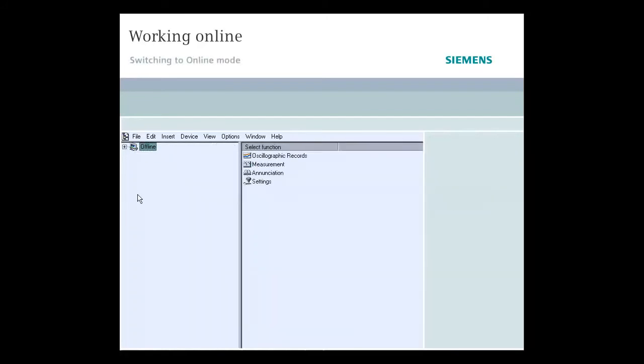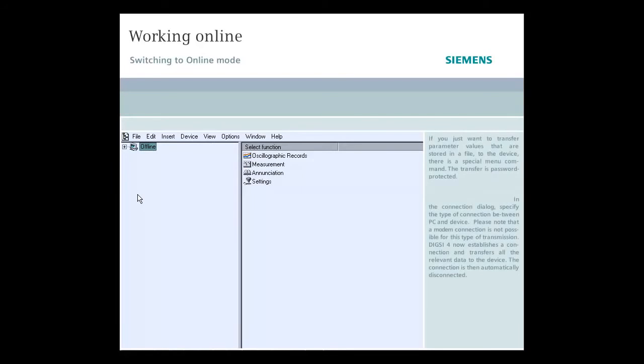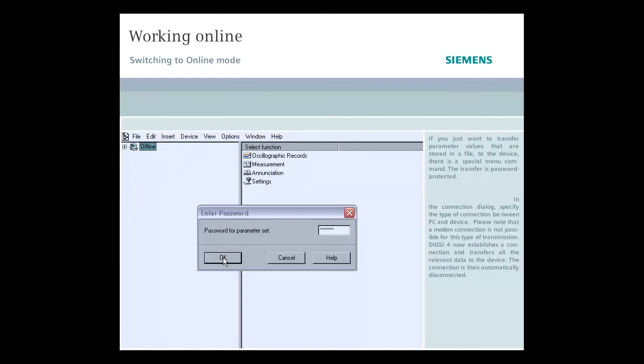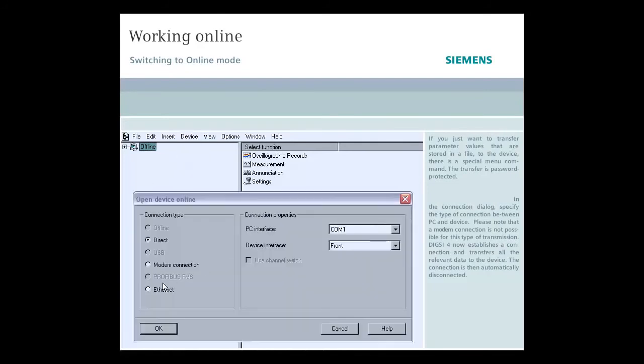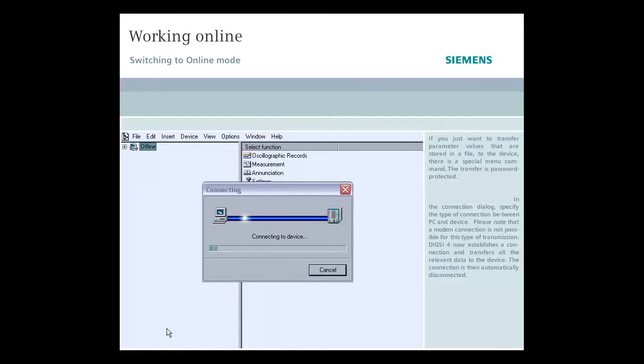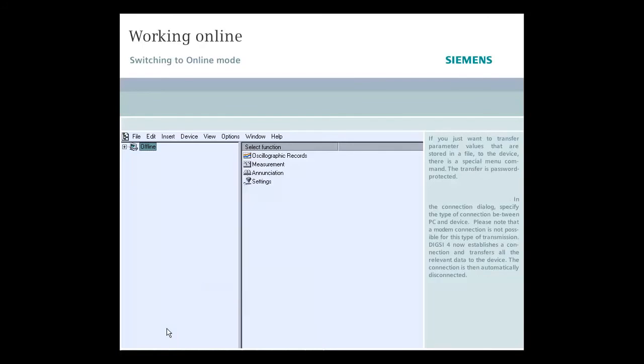If you just want to transfer parameter values that are stored in a file to the device, there is a special menu command. The transfer is password protected. In the connection dialog, specify the type of connection between PC and device. But please note that a modem connection is not possible for this type of transmission. DIGSI 4 now establishes a connection and transfers all the relevant data to the device. The connection is then automatically disconnected.